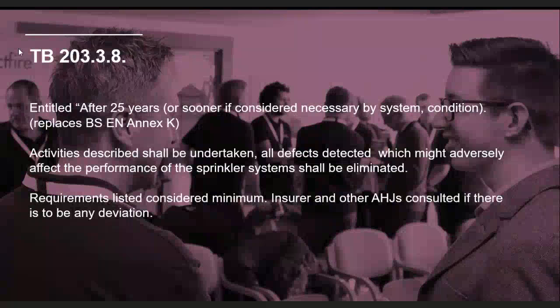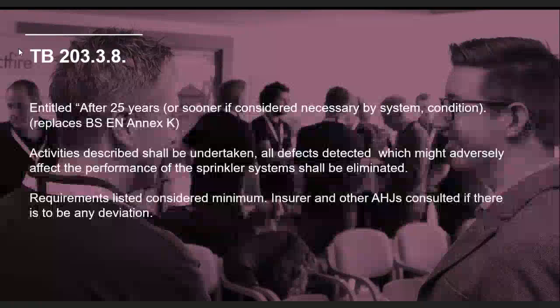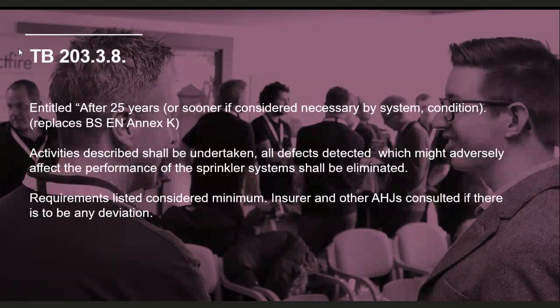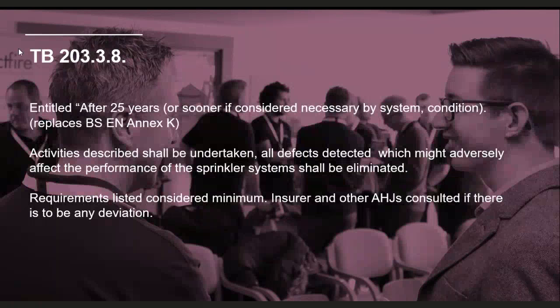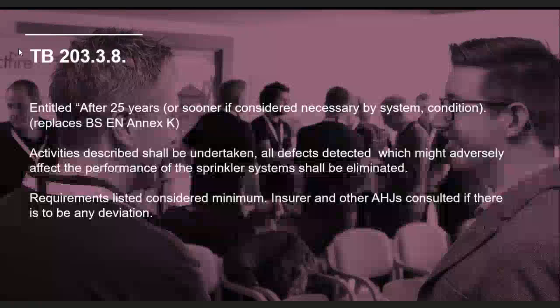Or sooner if considered necessary - why would it be considered necessary? I guess because you're seeing corrosion, pinhole leaks, you're concerned about the condition of the sprinkler heads for whatever reason. Maybe one has triggered in a non-fire situation, maybe it's malfunctioned, or when you open a drain valve you're getting a lot of mud, silt and stones coming through. So if you've got concerns about the condition of the sprinkler system, you can bring this 25-year inspection forward and do it sooner.